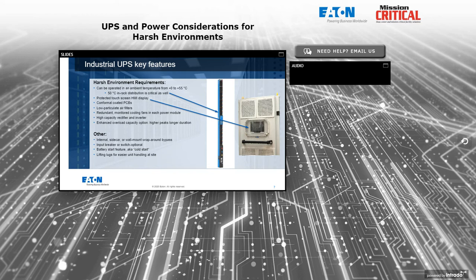Enhanced overload capacity, the same idea, at least optionally. I need to be able to handle a higher overload peak for a longer duration, and make sure that matches the application. One of the things that means is that you're looking at pumps and motor loads and moving assembly lines in a factory, compressors for air conditioning and cooling and heating. Those kinds of things are more likely to be placed on the output of the UPS. So we need to know up front what the worst case condition is in terms of inrush, and make sure the UPS is sized to handle that, even when it's running on batteries and has no utility present, or transitions to bypass if it gets overloaded. So these are sometimes complicated questions that need to be addressed early on in the process.